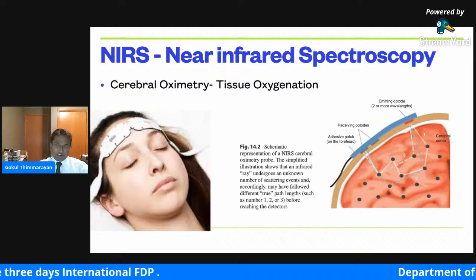When it passes through the tissues and receives the scattered light, from the variation in the light wavelength it receives after passing through the tissues, we are able to calculate the amount of oxygen in the tissues. So it's a step further in detecting tissue oxygenation, apart from checking the saturation of oxygen in the blood. This principle, Beer-Lambert law, with absorption of wavelengths through the material, is utilized in multiple scenarios: pulse oximetry, co-oximetry, and near-infrared spectroscopy.